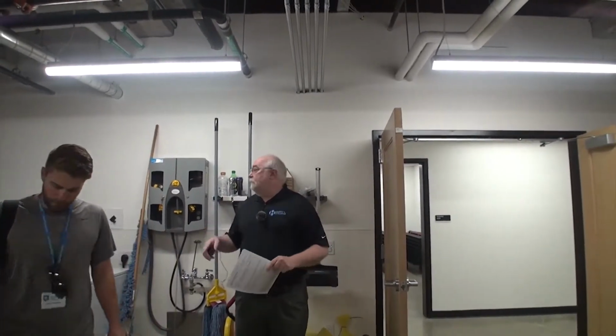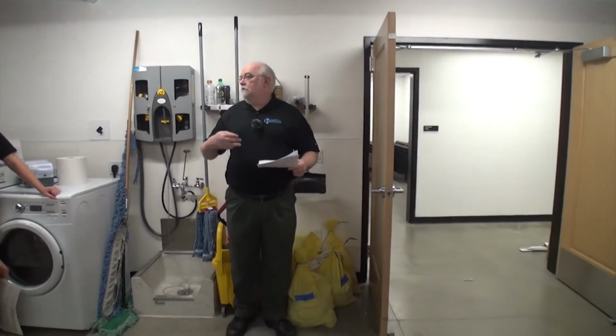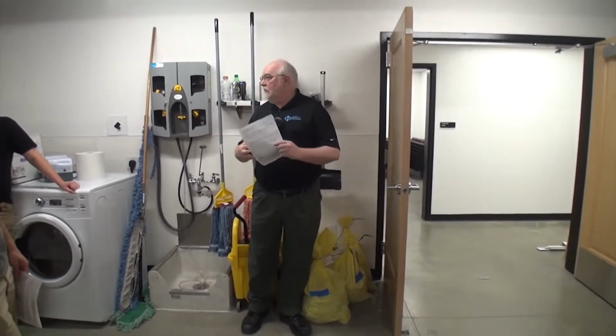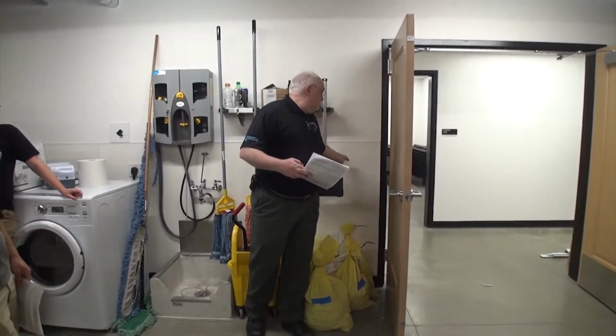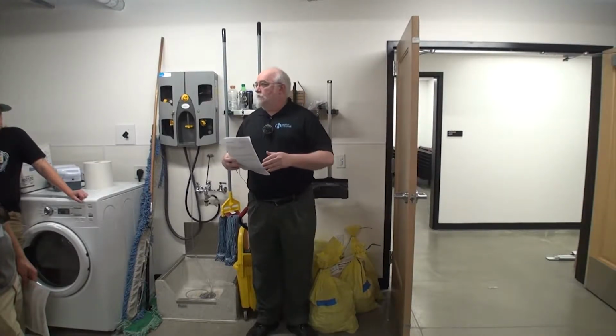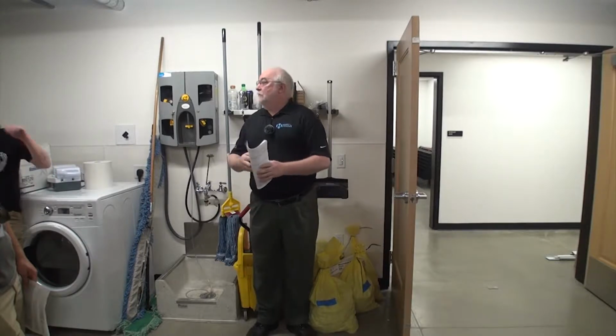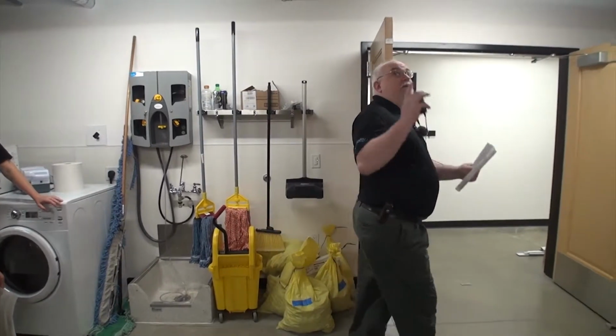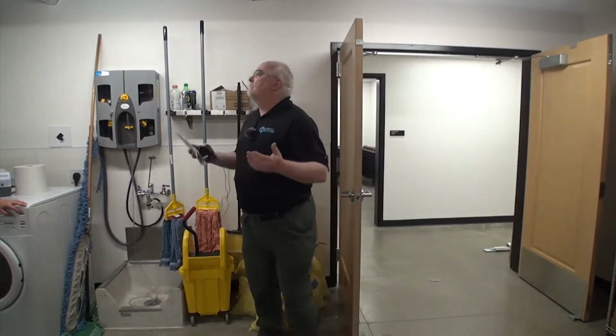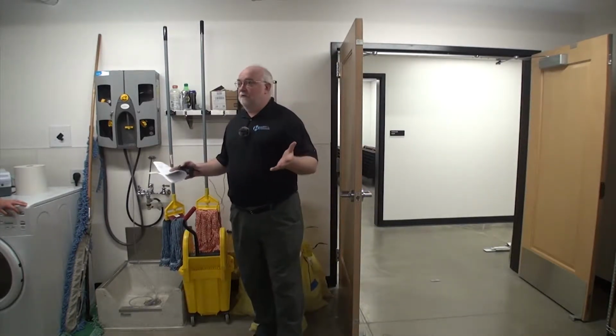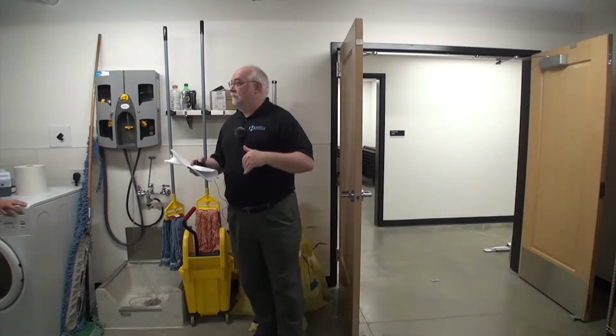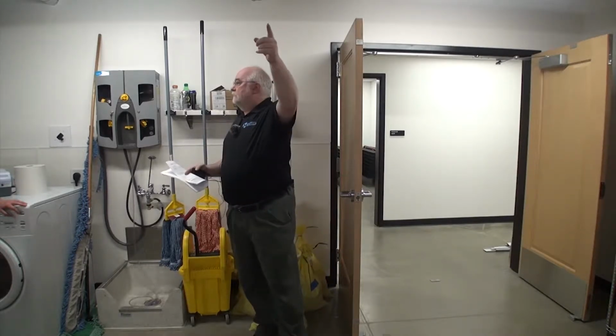So storage rooms are, my cheat sheet here, set to occupancy mode, and they have a 10-minute timeout. So 10 minutes after they don't see anything, the lights shut off automatically. Standard on-off switch, lights are going to go out, back on. Storage, we were given a fairly limited number of choices, so all of the storage rooms should act the same. Oh yes, sorry, there's no photocells, there's no exterior daylight to impact it at all. And the 10 minutes was off of the occupancy sensor.